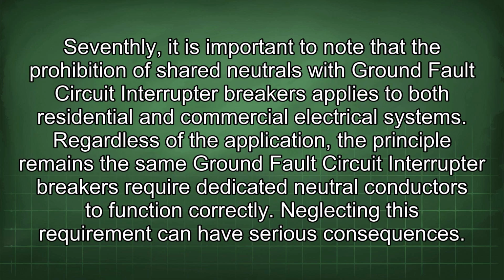Seventhly, it is important to note that the prohibition of shared neutrals with ground fault circuit interrupter breakers applies to both residential and commercial electrical systems. Regardless of the application, the principle remains the same. Ground fault circuit interrupter breakers require dedicated neutral conductors to function correctly.